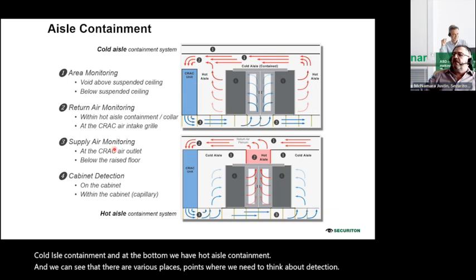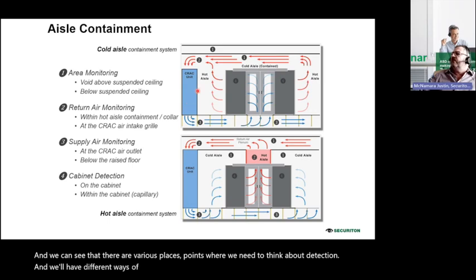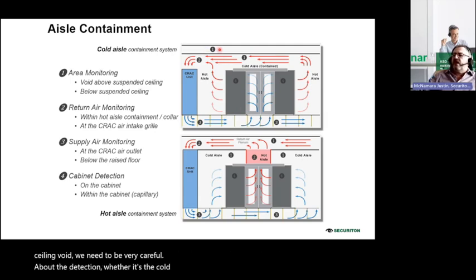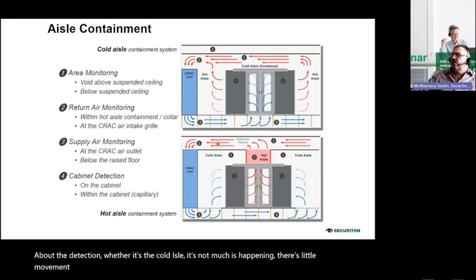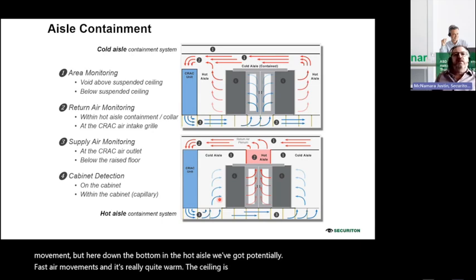We'll have different ways of looking at the detection policy, whether it's up here in a ceiling void. We need to be very careful about the detection, whether it's the cold aisle, where not much is happening and there's little air movement, or down at the bottom in the hot aisle, where we've got potentially fast air movements and it's really quite warm. The ceiling is being used as the return air plenum.